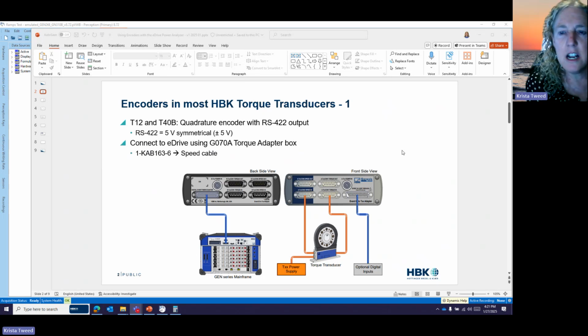Very straightforward. When you buy an eDrive bundle from HBK, it includes what we call the G70 torque adapter box. And this box serves two purposes. It converts the differential symmetrical RS422 output of the torque transducer into a TTL single-ended signal that the eDrive power analyzer can support. And the second purpose is that it splits that signal so that you can send those torque and speed signals directly to your automation system rather than having it just go to eDrive.